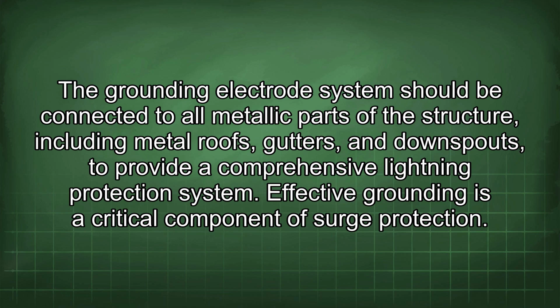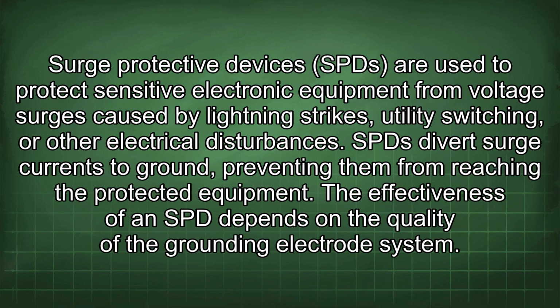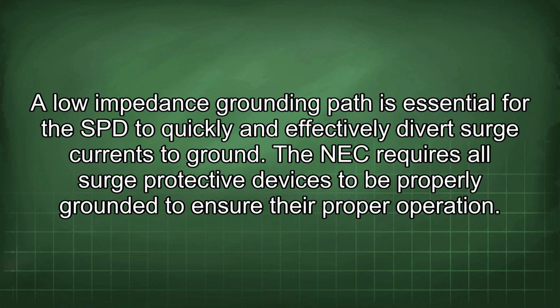Effective grounding is a critical component of surge protection. Surge protective devices (SPD) are used to protect sensitive electronic equipment from voltage surges caused by lightning strikes, utility switching, or other electrical disturbances. SPD diverts surge currents to ground, preventing them from reaching the protected equipment. The effectiveness of an SPD depends on the quality of the grounding electrode system. A low impedance grounding path is essential for the SPD to quickly and effectively divert surge currents to ground. The NEC requires all surge protective devices to be properly grounded to ensure their proper operation.